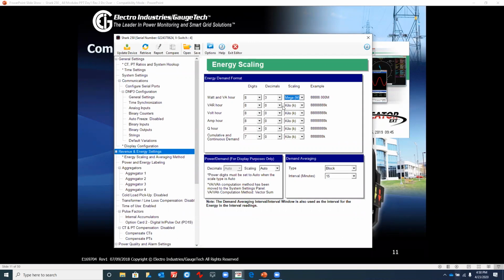But this is where you would do your setting for register display, energy scaling, or the register on the front of the meter, the number of digits you want to see. Power demand for display purposes: this is an area where you would set your demand to automatically scale for display purposes. So it's pretty self-explanatory. And demand averaging, I mentioned this briefly, has 2 types: block averaging and rolling. Block is basically if you were to store the average energy over a certain period. In this particular case, it would be 15 minutes. So whatever energy is stored in that 15 minutes, the meter would collect that bundle of energy, store it in the 15 minutes, and that's considered a block.